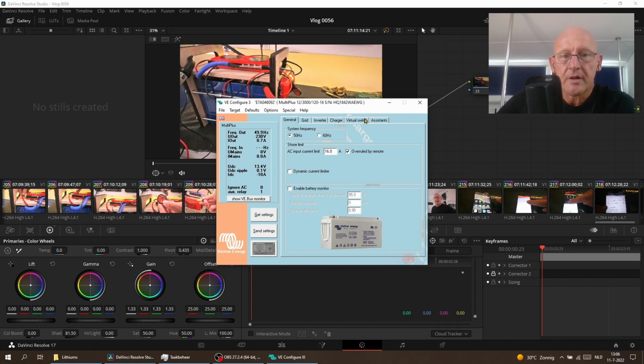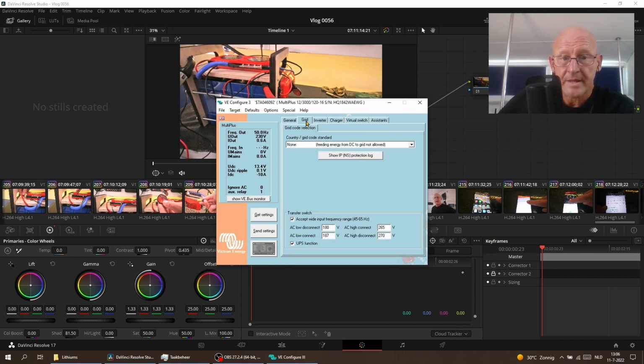We have a few tabs here. General, you can choose 50 or 60 Hertz. AC input current limit is 16 amps, the usual maximum amperage. The rest isn't important, I'll just tell you what I understand and what we use to change the settings of the Multiplus.